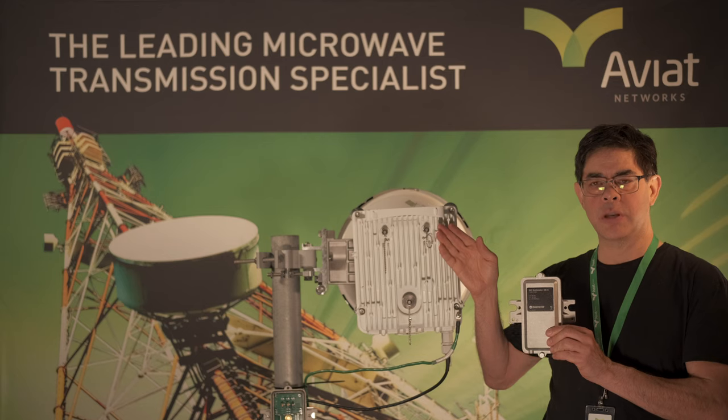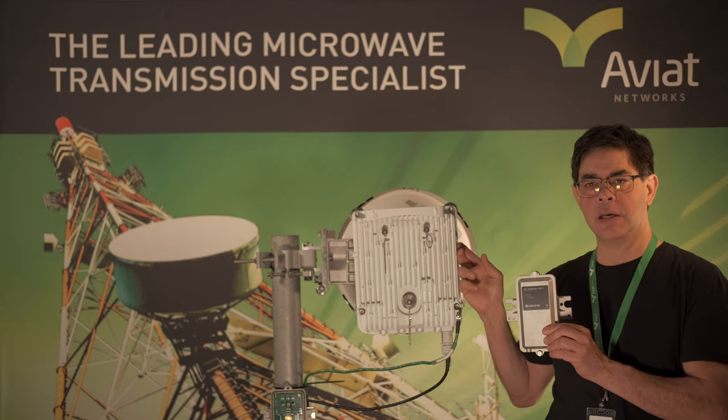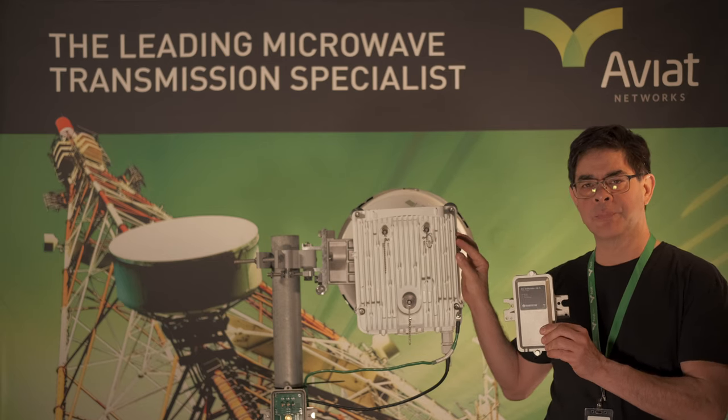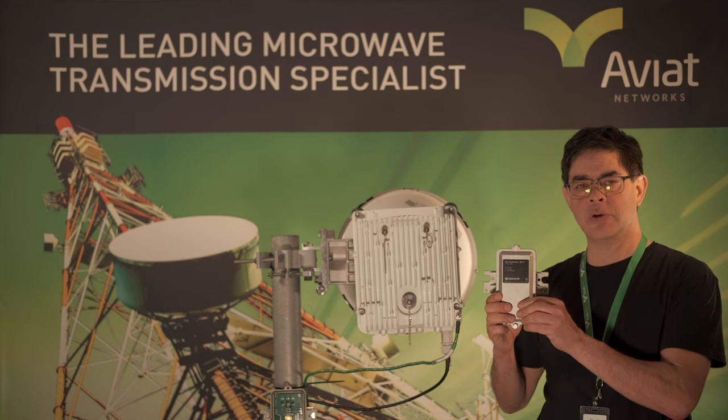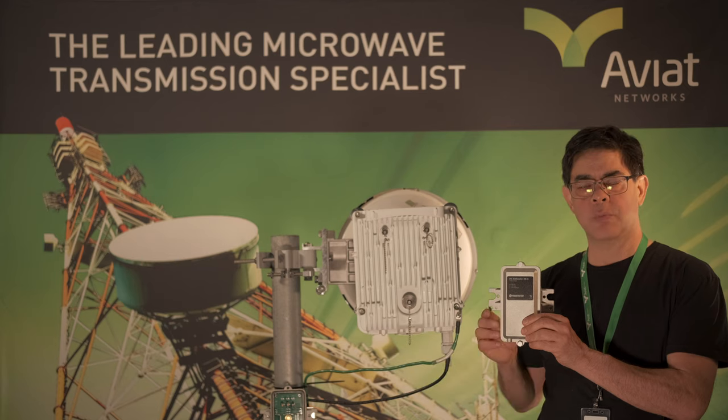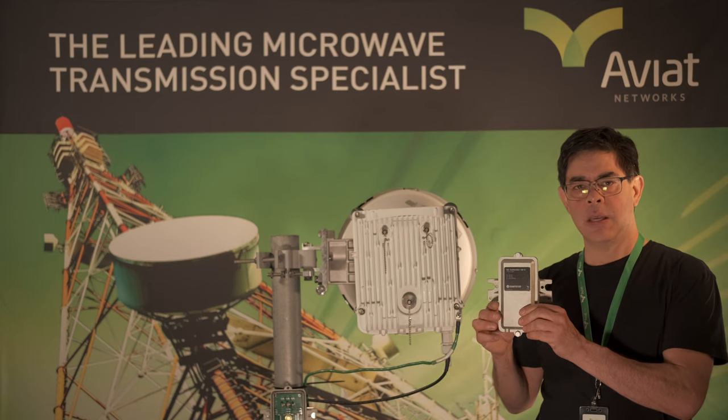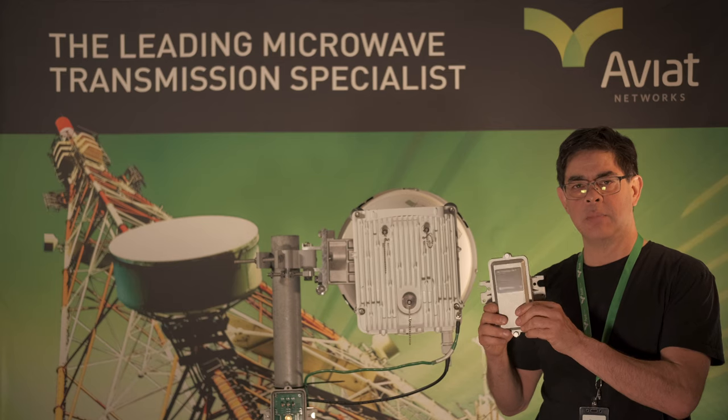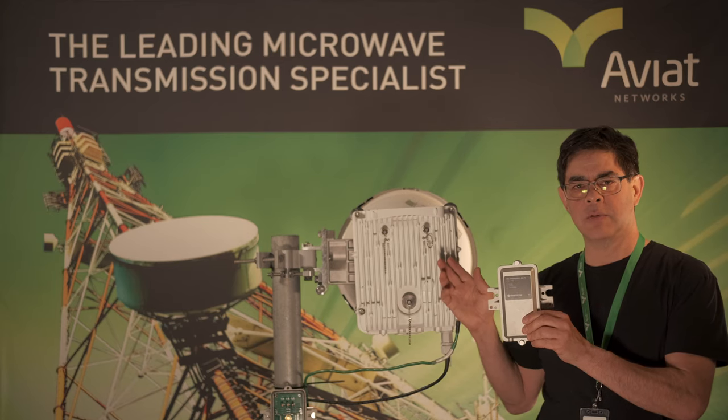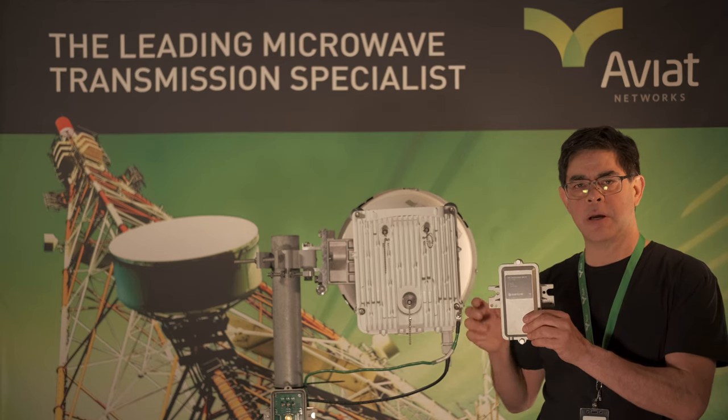Now, the WTM radios have got built-in surge protection on the DC line, but they're internal to the radio. A lot of times, people will put an external surge suppressor near the radio, and this will protect the radio from surges. In the case of a lightning strike, the surge arrestor may burn out. That can be easily replaced, rather than having to take the radio down and swap it out for a new radio.